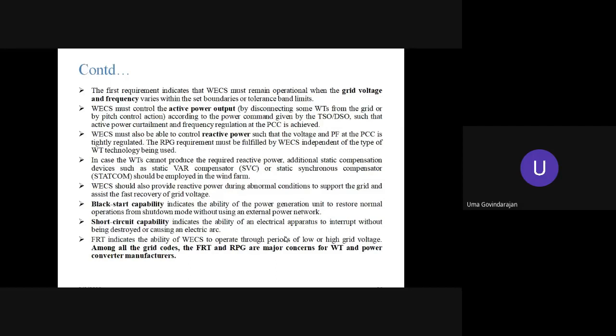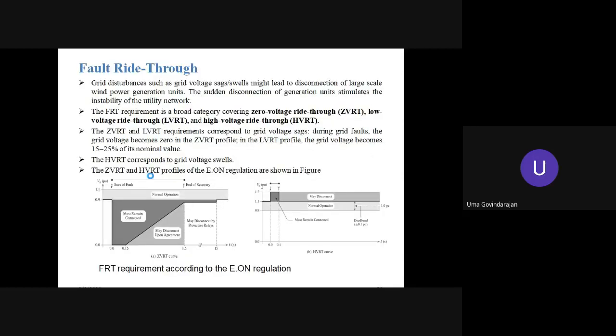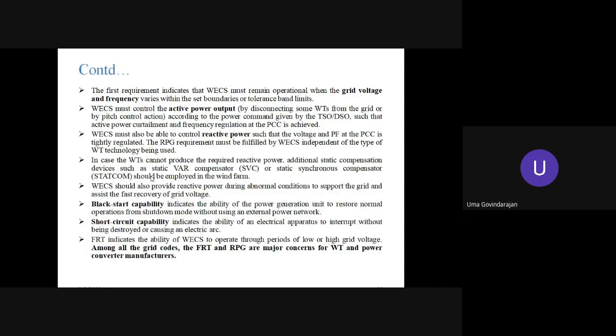Okay, the RPG requirement must be fulfilled. It is very important, and must be fulfilled independent of the type of wind energy technology used. So it is very important that the voltage profile at the grid is maintained by doing the reactive power control of the WECS. Out of all the points, reactive power control at the interface point is a very, very important point.